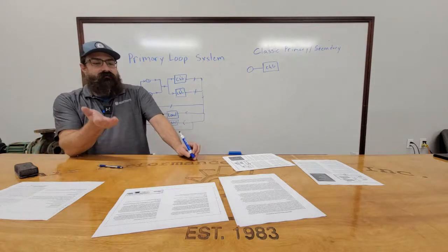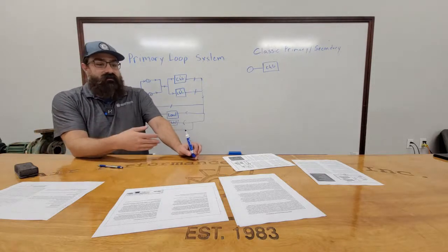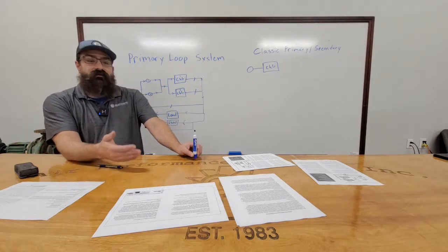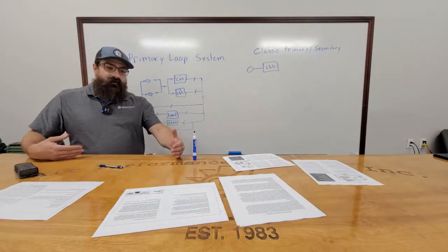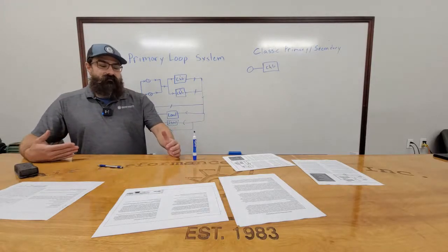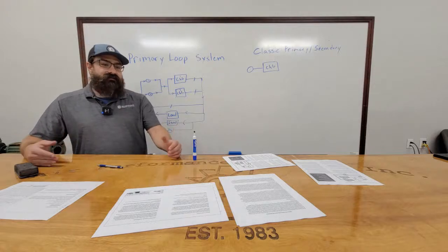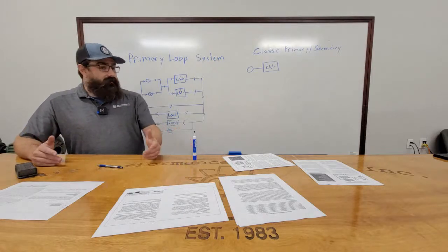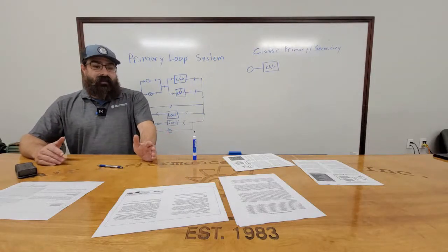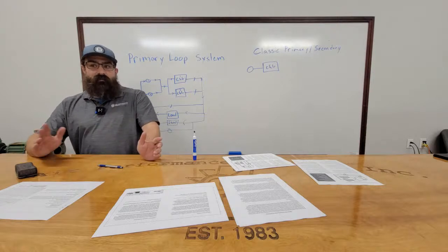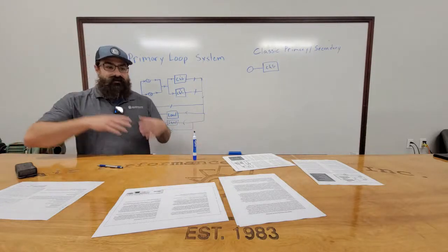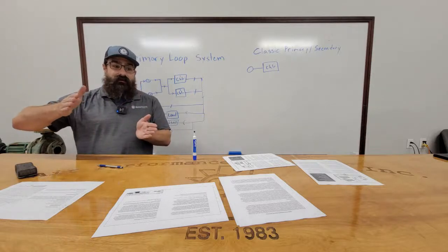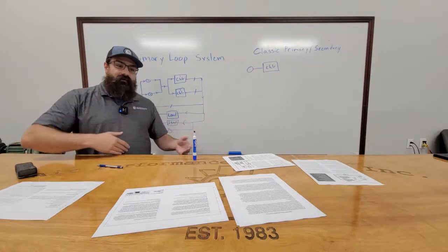Most of the time your flow is going to be set by that kind of stuff, and usually on startup, right? Like when the chiller is installed, that kind of stuff is done. Now, 20 years down the road, stuff's been monkeyed with, things have been moved, valves have been changed. That stuff gets all out of whack. And the building I'm talking about definitely has that problem. They actually have two brand new Carriers, but the rest of the building is out of whack. They set the chillers for what they needed, but the rest of the building is out of whack.